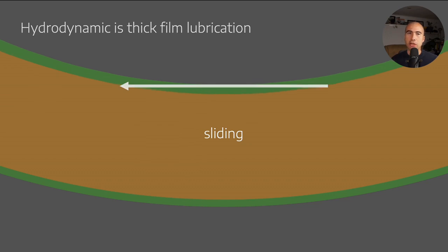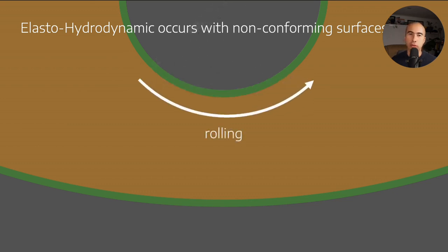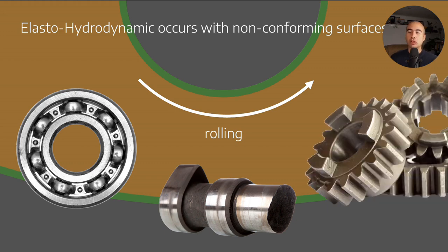Elasto-hydrodynamic lubrication happens with non-conforming surfaces where one radius is significantly different from the other. Instead of sliding motion, we have rolling motion. Examples include rolling element bearings, cams, and gears. This is the main thing that makes lubrication of rolling element bearings different from plain bearings.